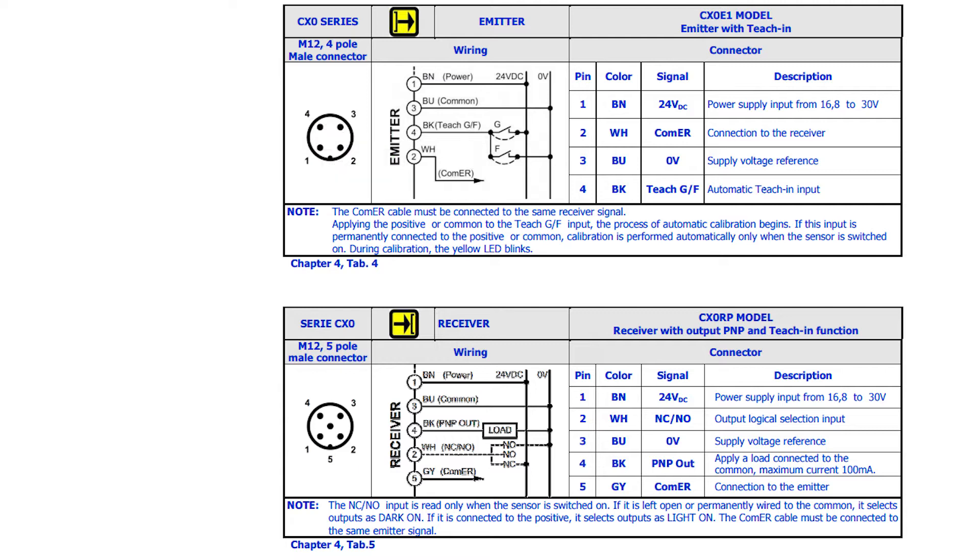Now let's wire the receiver. The receiver has 5 connections: brown for positive voltage and blue for negative voltage or common to power the sensor. The black wire on the receiver should be connected to your output device and wired as PNP.